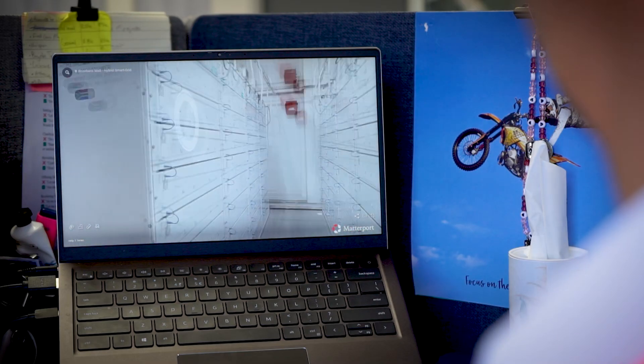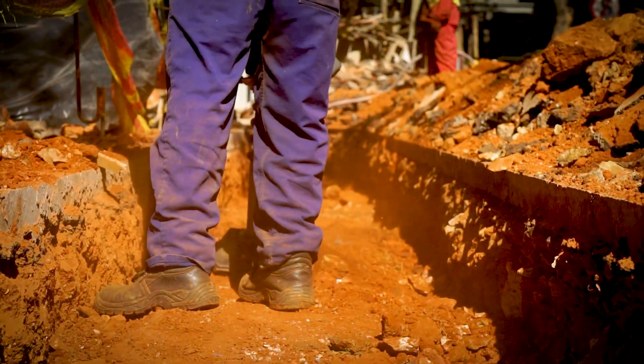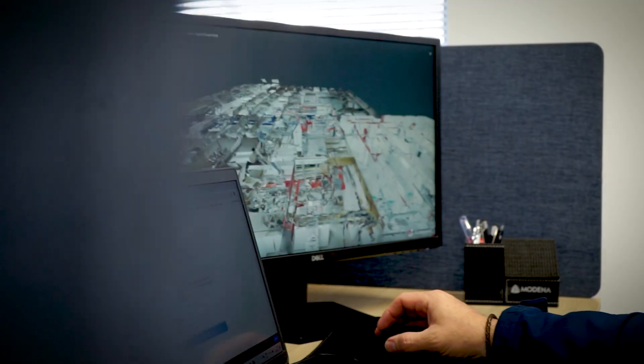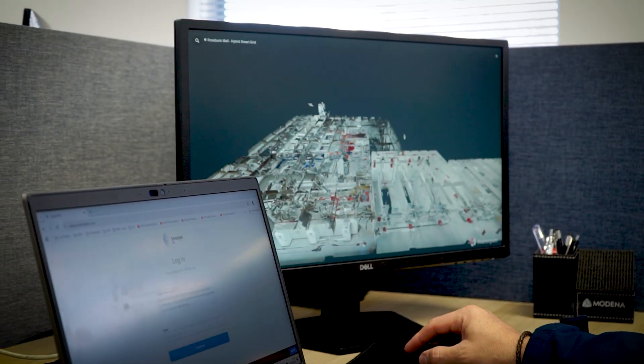The battery room was originally designed in a 90-degree orientation. It was only through using Revit and clash detection that we realized there was a major clash. We probably saved HyProp about 3 million rand by catching that catastrophic clash — because it simply was not going to fit. Before the first hammer came down or the first bucket of concrete was poured, we had already captured that, changed the design, and issued it on the design lines.